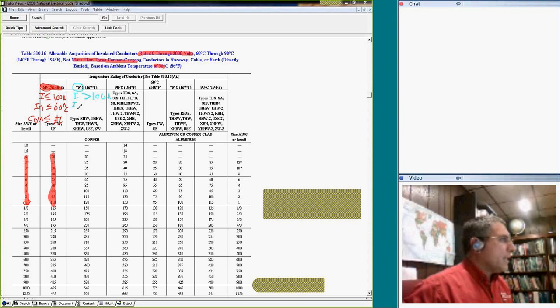Insulation, IN stands for insulation. If your insulation is more or equal to the 75-degree column, then you're going to default to the 75. Okay. And the last one is conductor. If your conductor is more than number 1 conductor.